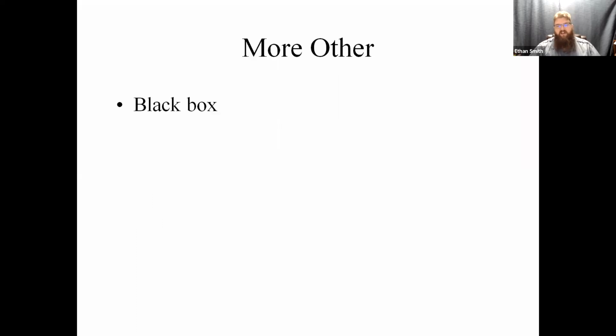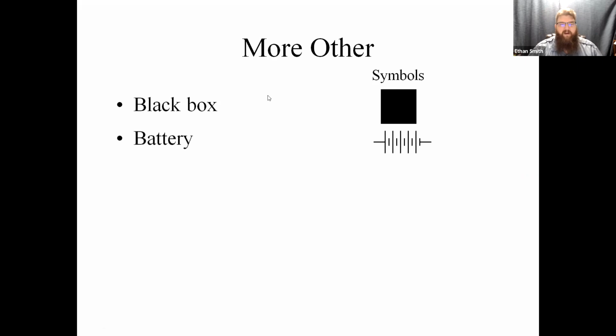Other devices that you'll see on wiring diagrams is the dreaded black box. Looks like that. Usually has some wires poking out of it. This is generally used to designate solid state electronics that you can't do anything with. That's a battery. Hot surface igniters. These are just heaters, guys, so they ohm out or they don't. Every hot surface igniter has a different ohm rating, so refer to your OEM for that.